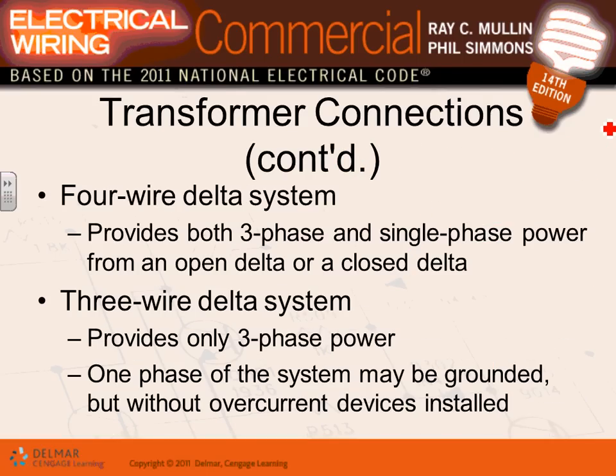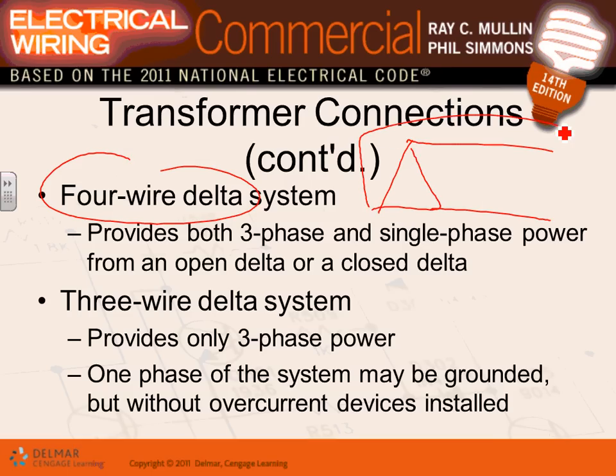Typically, we don't use it in residential. The most common one, like I said, is the four-wire delta. They take a delta like this, and here's one wire, two wire, three wire, and they take the center of one of them, ground it, and they take a fourth wire. Here's your four-wire delta. Typically it's used in certain applications where you have a small amount of single-phase load and a huge amount of three-phase load, guys. Well houses and what not. Again, we will hit them in the industrial.